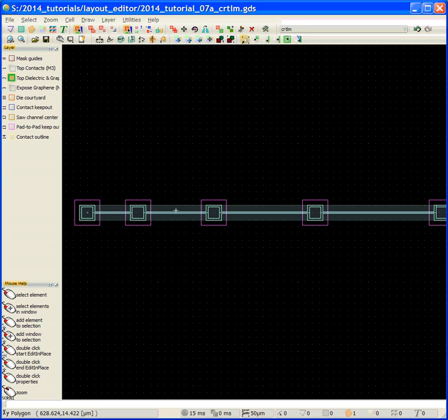This is double contact spacing, 3 times contact spacing, and 4 times contact spacing. And what you do is you measure between contact sets and plot the resistance of each one in a plot. So you have R, 2R, 3R, 4R, and if you go between this contact and this contact, you'll have 3R, and so on and so forth. So you can build a plot of what the resistivity is. And then where that line intersects the y-axis will tell you what the contact resistance is.